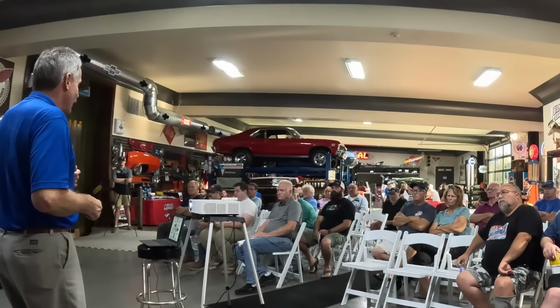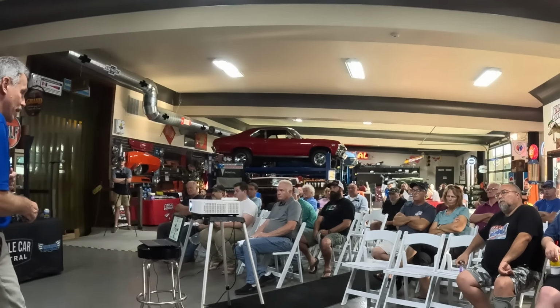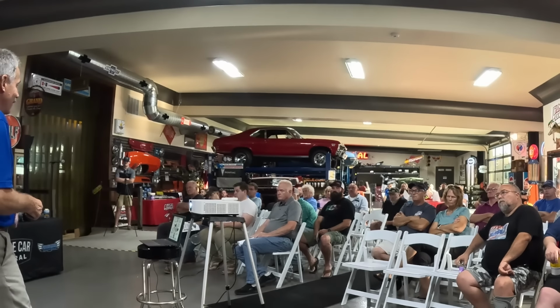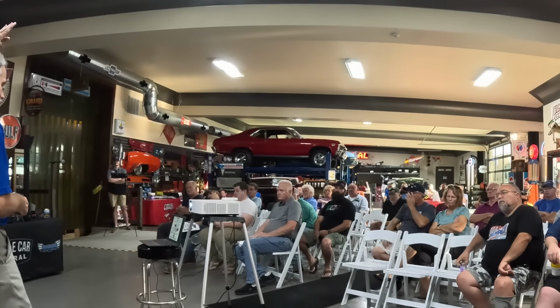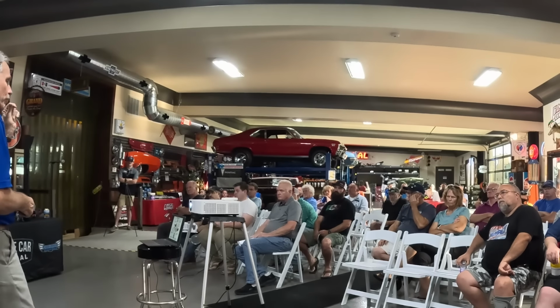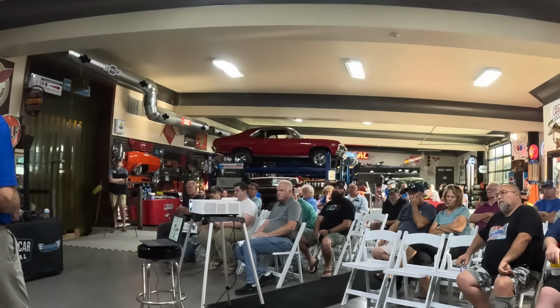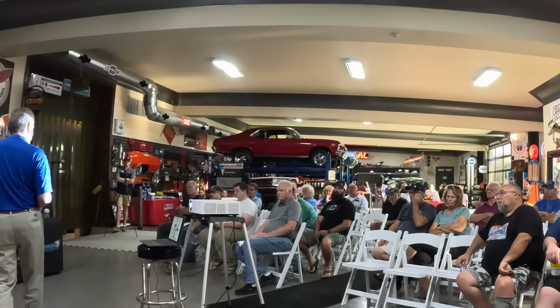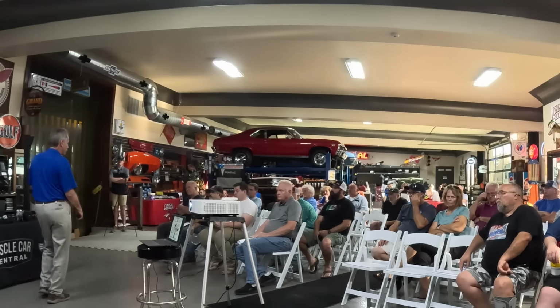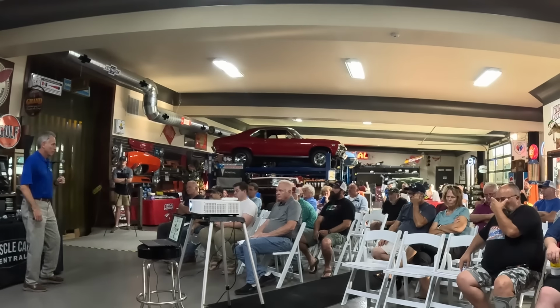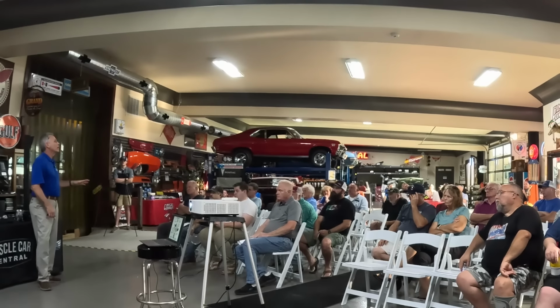So what's going to happen if you just have a binary switch is that pressure is going to shoot up and it's going to cut the compressor off. Now you're not going to be cool anymore because the compressor's off, it's not pushing refrigerant through the system. We don't want that, we want airflow.